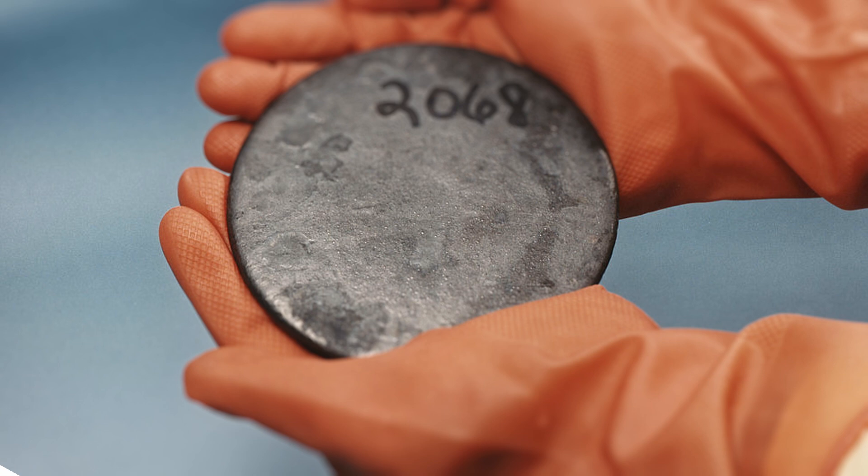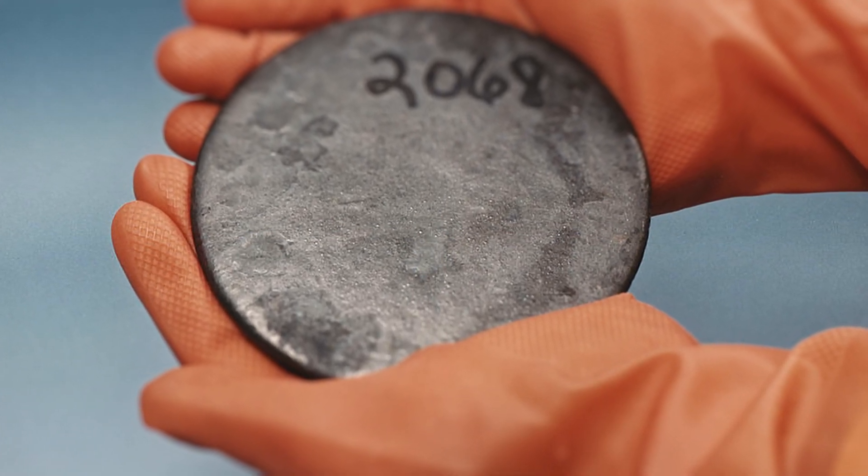The fuel used for the S-1W was enriched uranium that contained about 5% uranium-235. At this low of an enrichment, neutrons would need to be slowed down in order to increase the probability of a fission event and sustain a chain reaction. In pressurized water reactors, the high-pressure water is used to moderate neutron energy by letting them undergo multiple collisions with the light hydrogen atoms in the water, causing them to lose kinetic energy in the process. The water moderator also serves as a passive self-regulating mechanism, as its ability to moderate neutron energy is reduced as it heats up and increased as it cools.